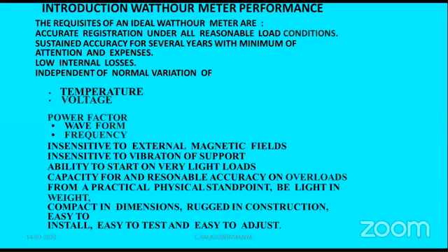From the practical physical standpoint, the meter will be light in weight, compact in dimension, rugged in construction, easy to install, easy to test, and easy to adjust. You can't adjust an electronic meter. All adjustments are provided in the mechanical meters, like the brake magnet adjustment, the inductive load adjustment, the light load adjustment, and the torque balancing adjustment. These are all the adjustments provided, because with more adjustments the meter becomes more fragile. It will not answer the question of whatever you want to make the meter more stable.